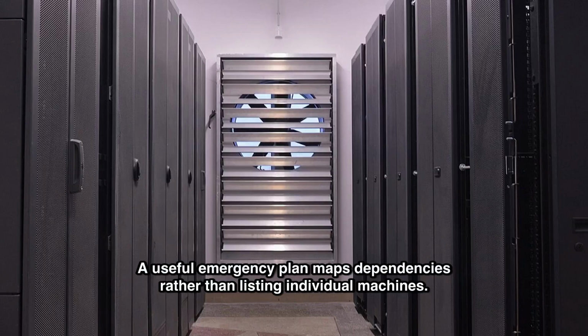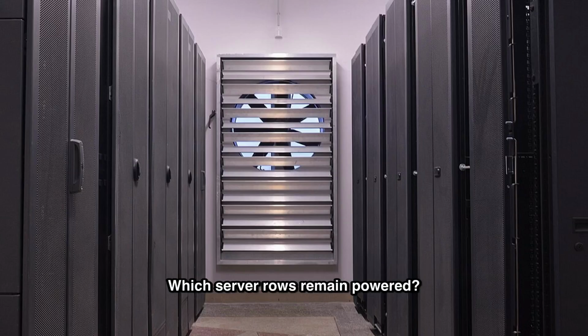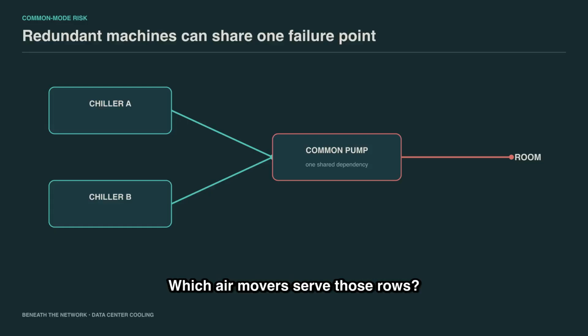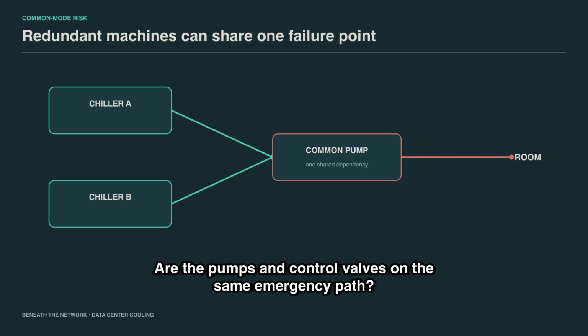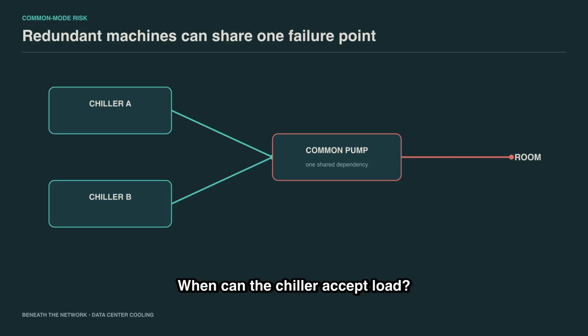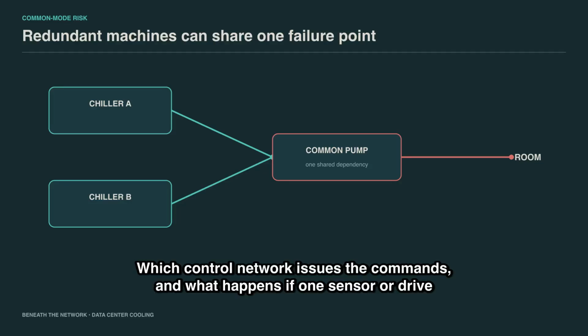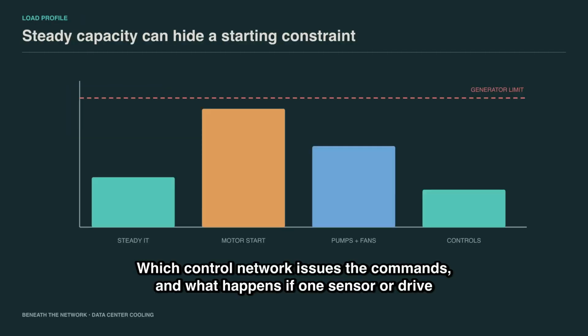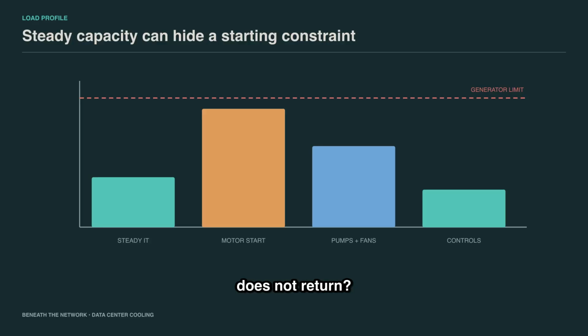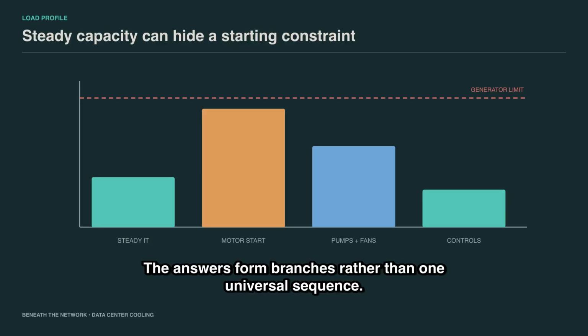A useful emergency plan maps dependencies rather than listing individual machines. Which server rows remain powered? Which air movers serve those rows? Are the pumps and control valves on the same emergency path? When can the chiller accept load? Which control network issues the commands? And what happens if one sensor or drive does not return? The answers form branches rather than one universal sequence.